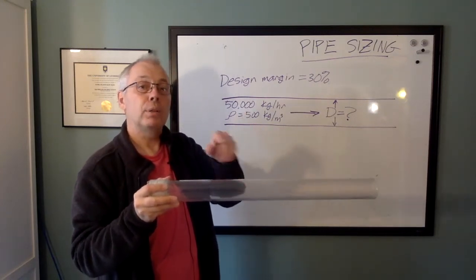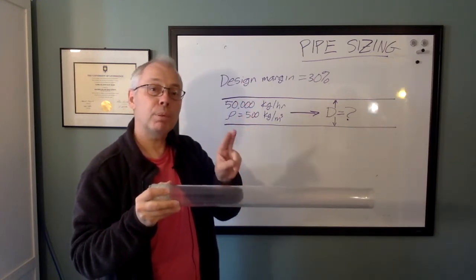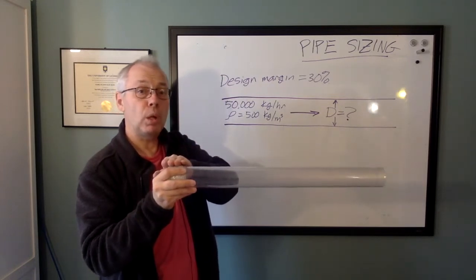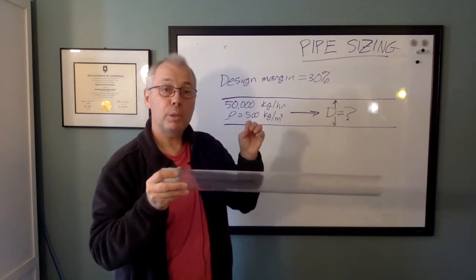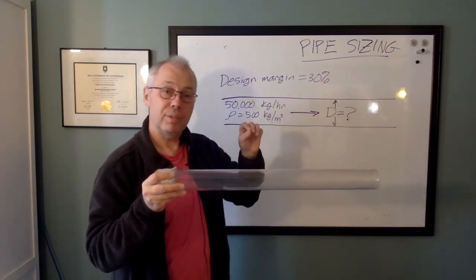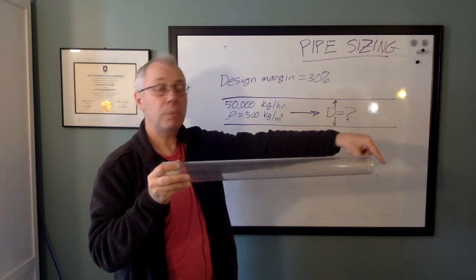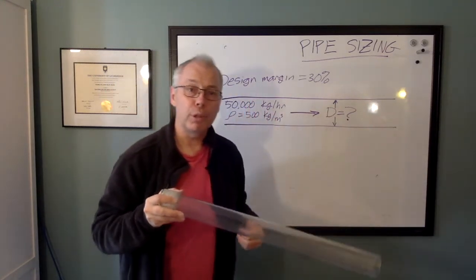That's criteria number one. That's a speed limit. Criteria number two is a little more interesting. And that is, if the pipe is too small, the pressure drop from the inlet to the outlet will be too high. And if it gets too high, whoever's on the outlet of this pipe will not be able to do their job. We'll look at criteria one first. Speed limit.